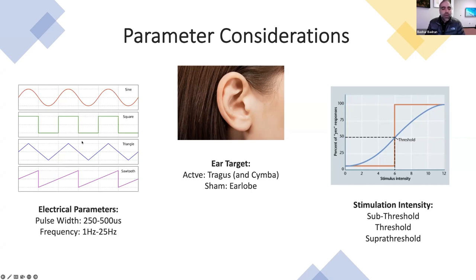Pulse width relates to when there is a positive or negative inflection of the electrical signal. It's the width from the rising edge to the falling edge of the waveform. So what we have here is a pulse width with a specific set time, and what we use is a time between 250 microseconds and 500 microseconds, which seems to be the most electrically efficient pulse width to activate nerves in the body.